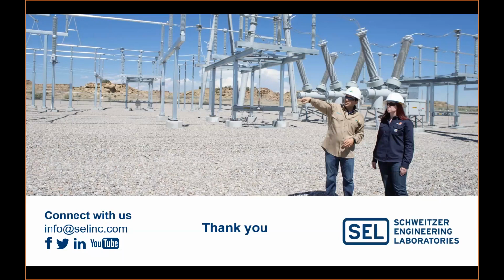For each millisecond that we save in the tripping time, for a bulk system, it means saving 1 megawatt in the transmission capability. You can think of saving 1 cycle as 20 megawatts more capability on that line, and it will save you from system stability issues as well. So this is one part: the faster, the better.